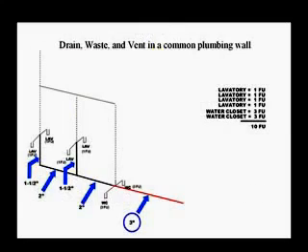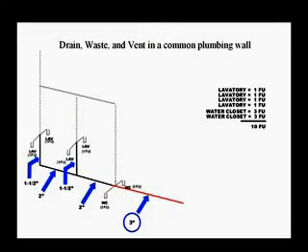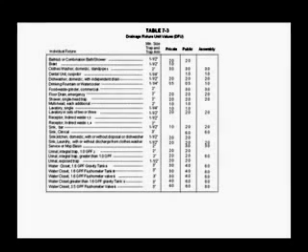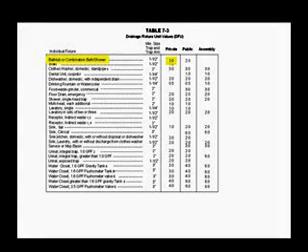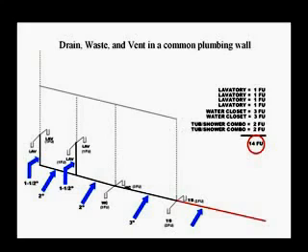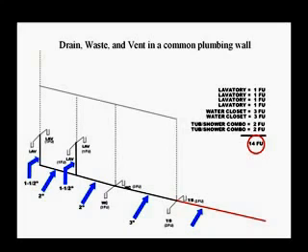This horizontal section of the building drain is sized up to 3 inch pipe. Let's add 2 combination bath and shower fixtures to the system. Refer to table 7-3. Locate bathtub and combination bath and shower and note that each fixture will add 2 fixture units. Adding these to the existing fixture units, we have a total of 14 fixture units.